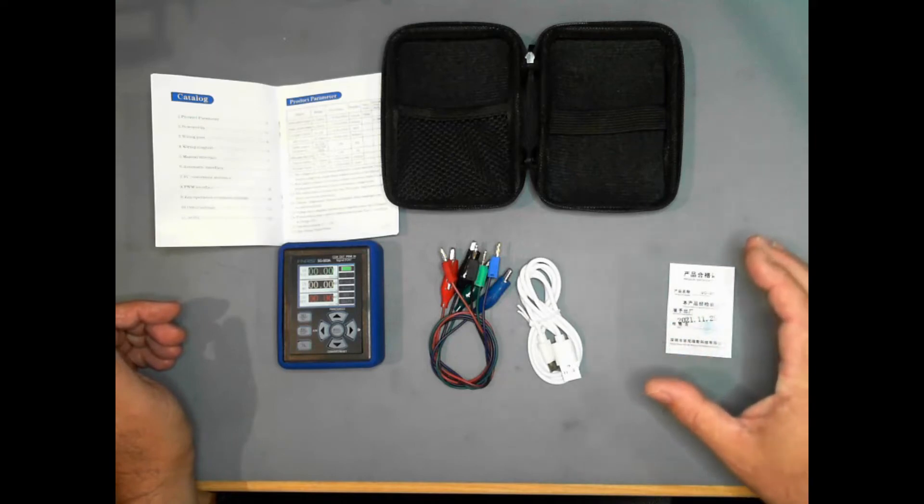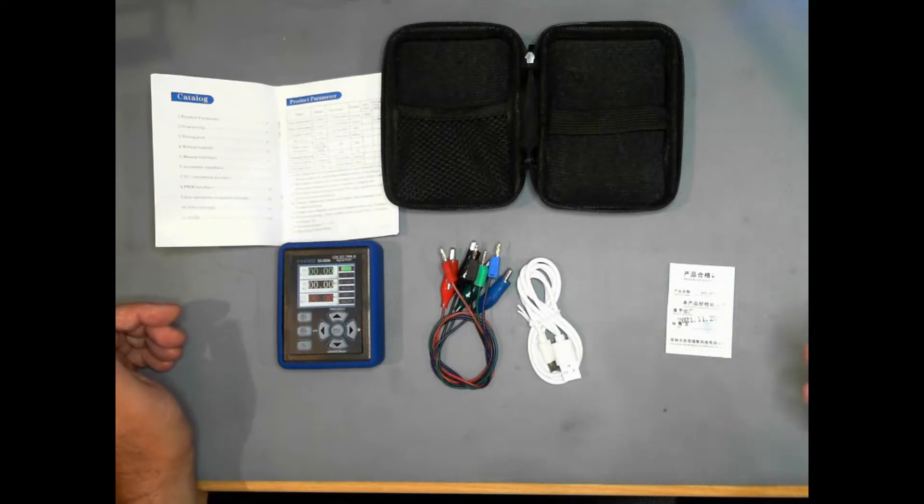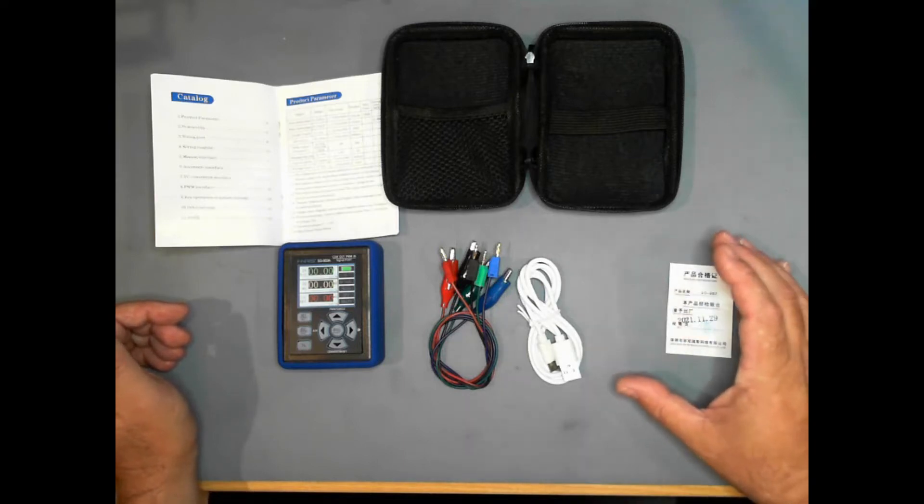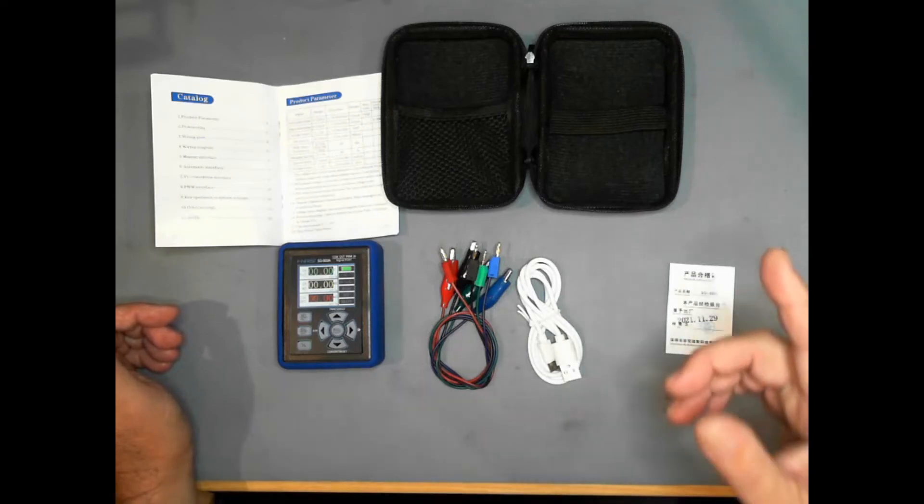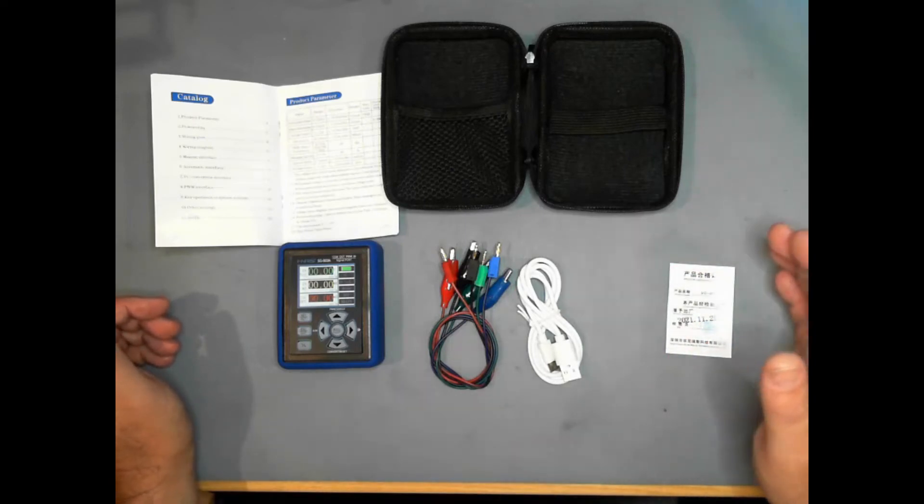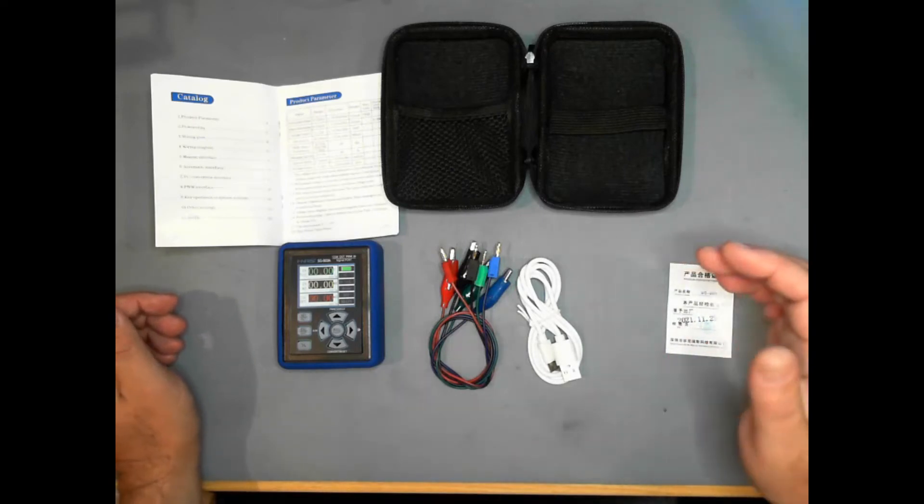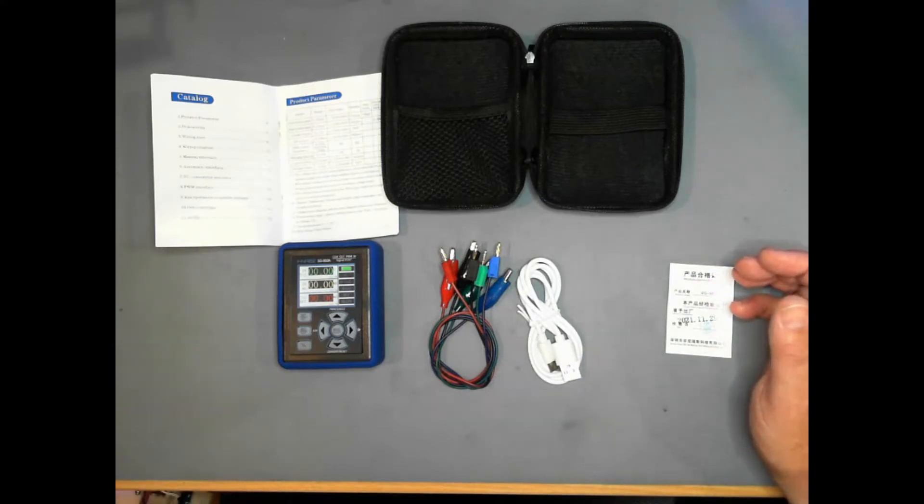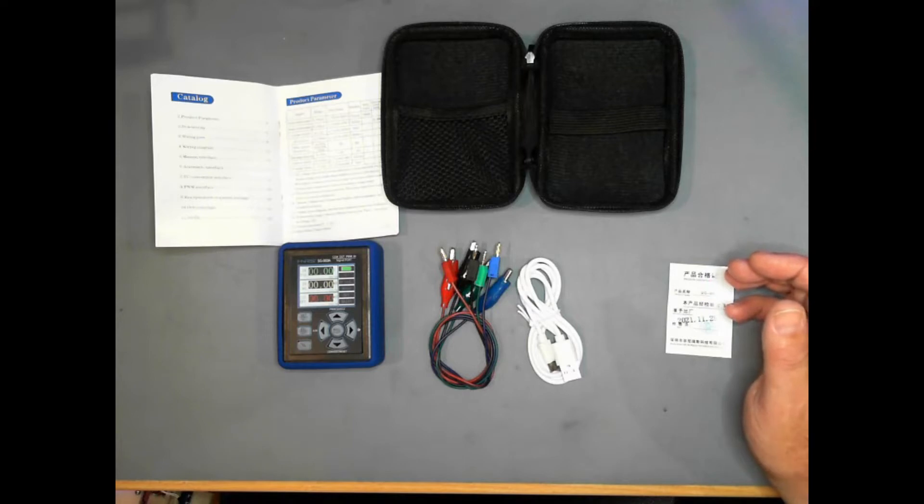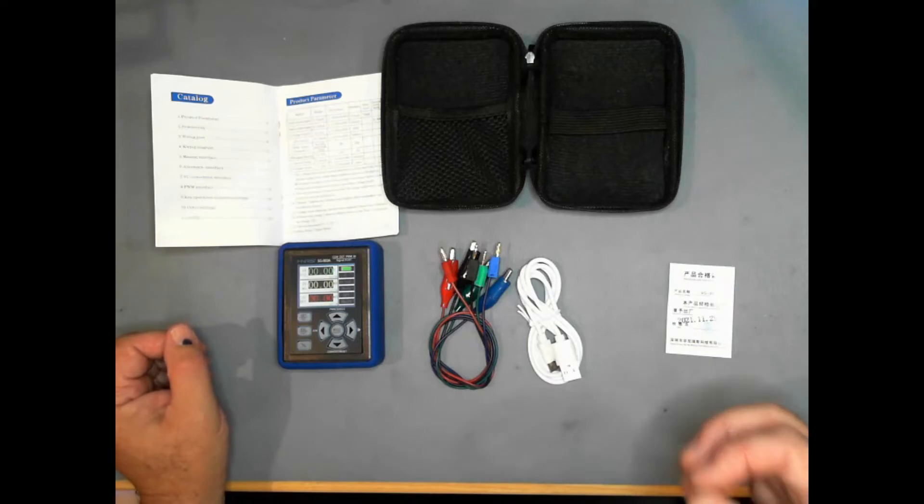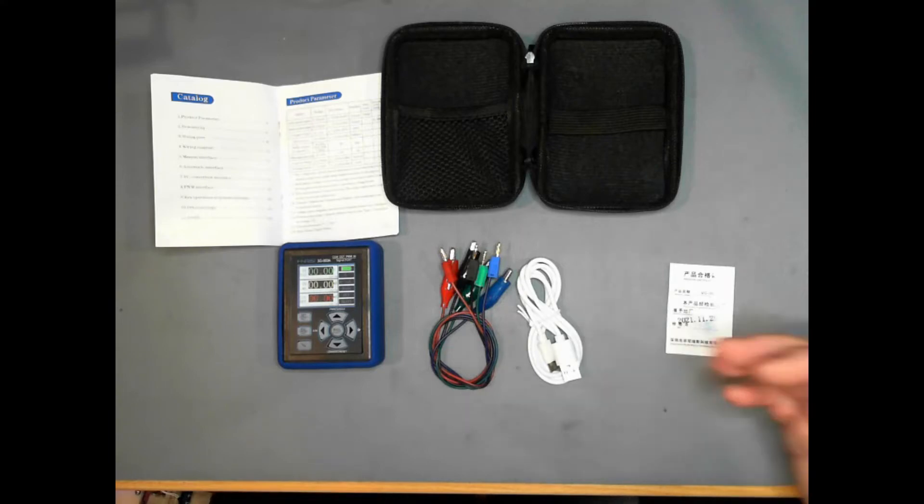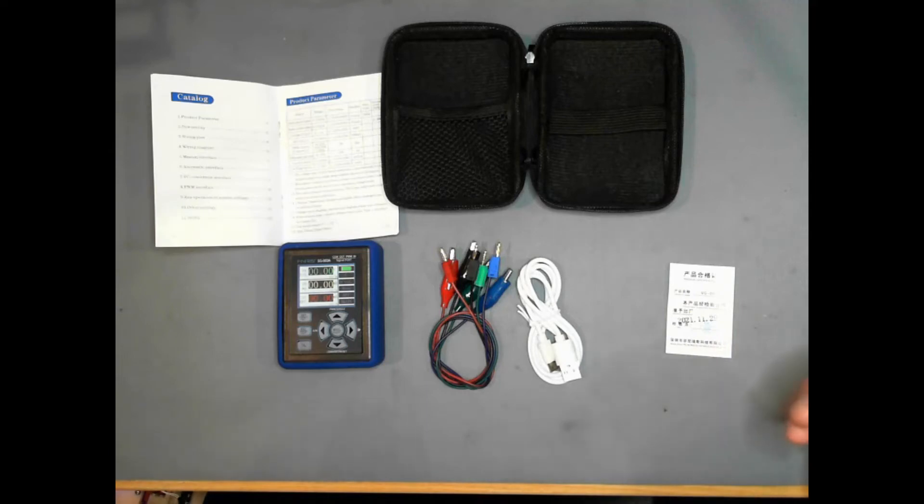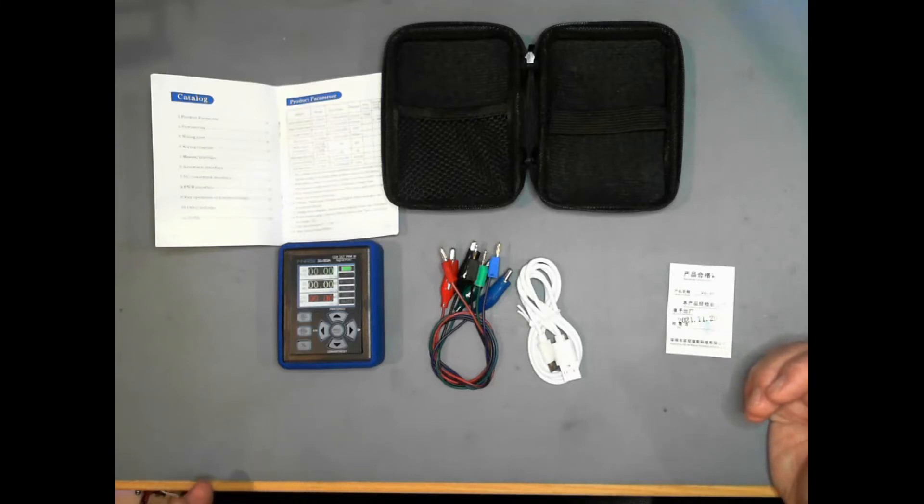A typical example of that is a pressure sensor. You can supply 24 volts down the line, typically it's 24 volts. The sensor at the end will use some of that power, up to 4 milliamps worth, to run the pressure sensor and its electronics. It will then add load so it will actually cause more current to flow on top of that 4 milliamp, in order to send a signal up to 20 milliamps worth.